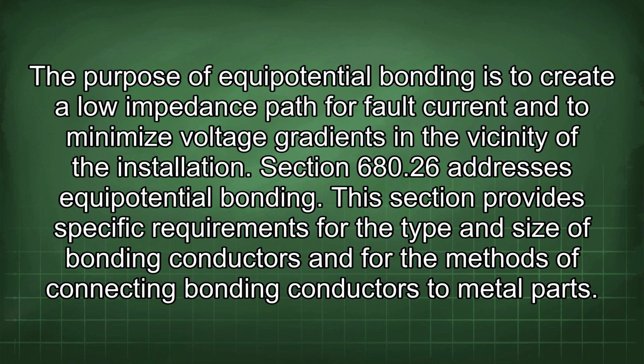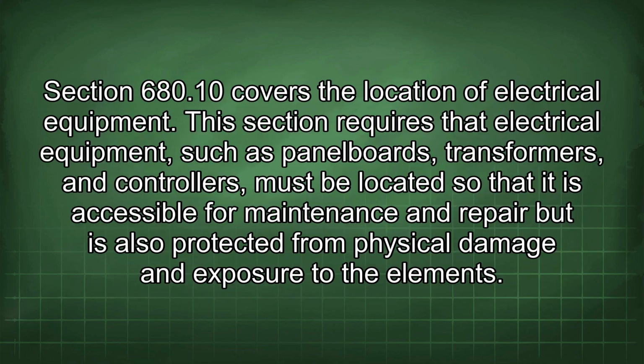680.26 addresses equipotential bonding. This section provides specific requirements for the type and size of bonding conductors and for the methods of connecting bonding conductors to metal parts. Section 680.10 covers the location of electrical equipment. This section requires that electrical equipment, such as panel boards, transformers, and controllers, must be located so that it is accessible for maintenance and repair but is also protected from physical damage and exposure to the elements.